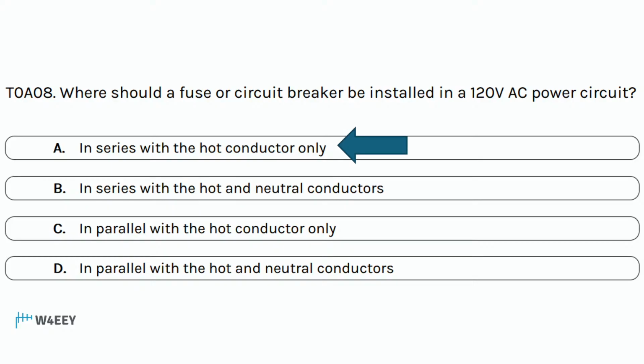Yes, in series with the hot conductor only. And the reason being is the hot conductor is the source of energy coming into the circuit, and you want it to blow there so that energy does not still reach the circuit. If you were to put the fuse on the neutral side, the fuse might blow, but the black wire is still connected to the circuit and still providing energy to that circuit. So if you stuck your hand in there, you'd have a problem. So that's why we always fuse the black or the hot conductor.